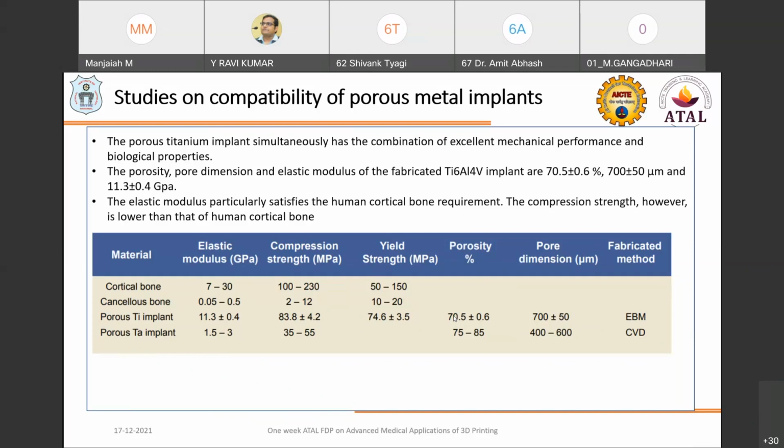And this elastic modulus particularly satisfies the human cortical bone, which is the requirement of the particular patient-specific implant, and the compression strength is lower than that of the human cortical bone. If you see this table with respect to the particular material, for cortical bone the requirement is an elastic modulus of 7 to 30, compression of 100 to 230 megapascal, and yield strength of 50 to 150.